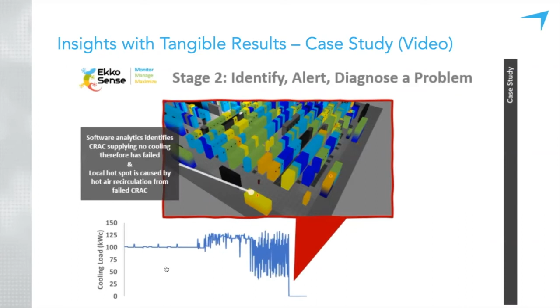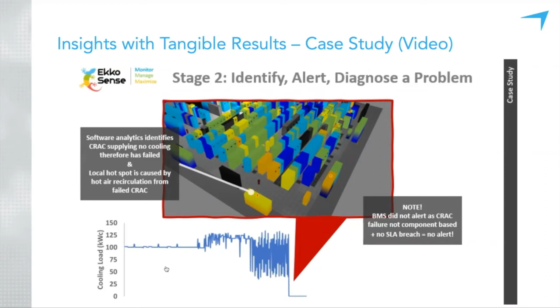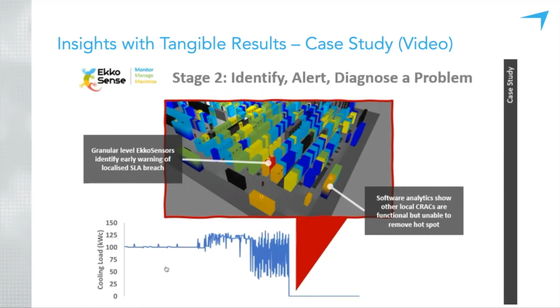Then over time, the situation degrades even further, and the cooling system in that corner actually fails, leading to an SLA breach and a fault. Up until that point, there were no alerts triggered by the BMS sensors until the very last moment. So this kind of output's given potentially days of additional warning time to show that something strange is happening to the cooling machine. And it allows everybody to get in place a fix prior to there being an outage.